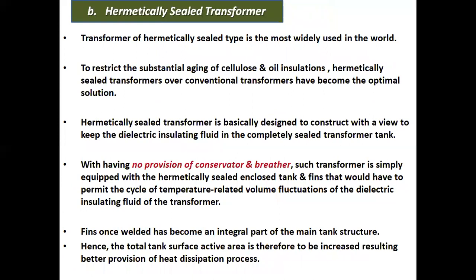Now, let's discuss the hermetically sealed transformer. The hermetically sealed type is the most widely used in the world. To restrict the substantial aging of cellulose and oil insulations, hermetically sealed transformers over conventional transformers have become the optimal solution. A hermetically sealed transformer is designed to keep the dielectric insulating fluid in a completely sealed transformer tank, without the provision of a conservator and breather.